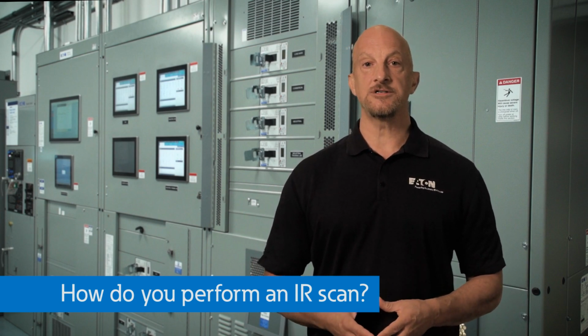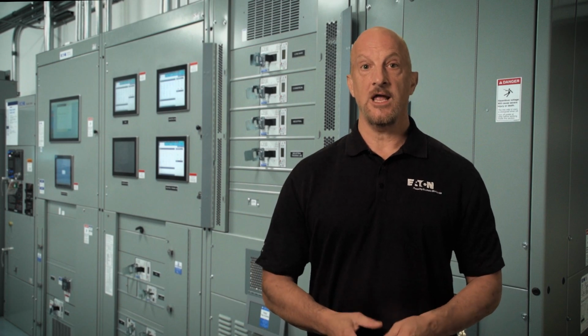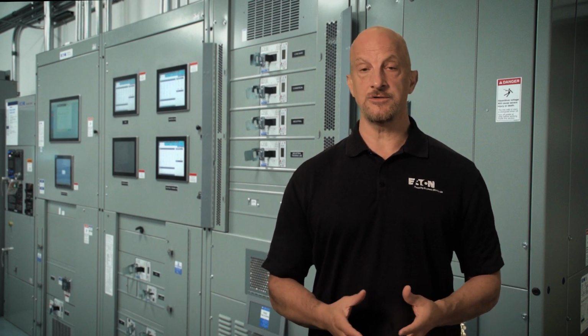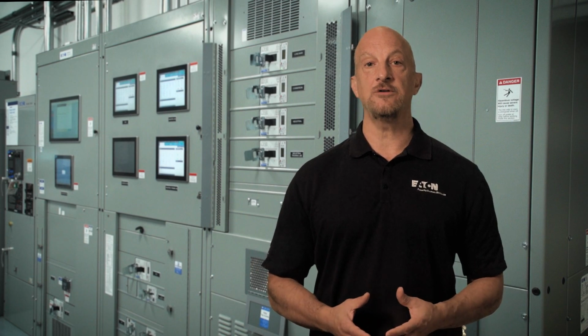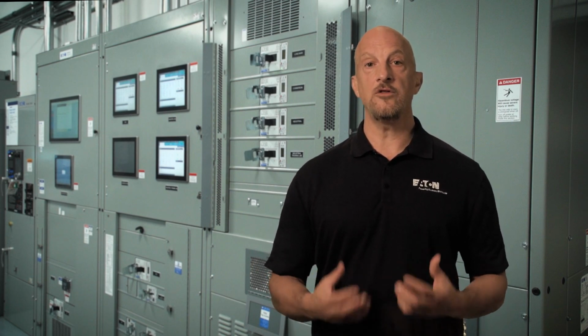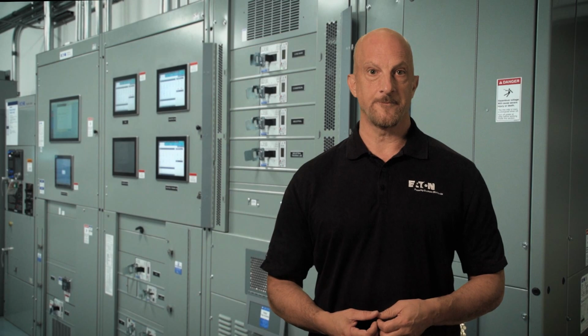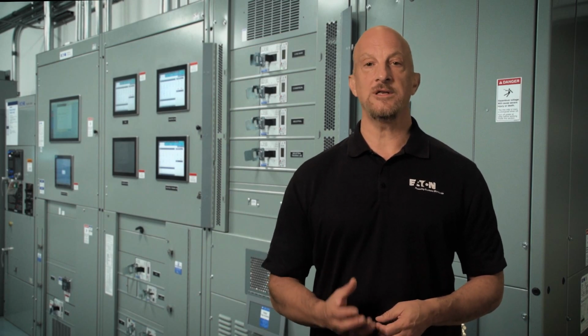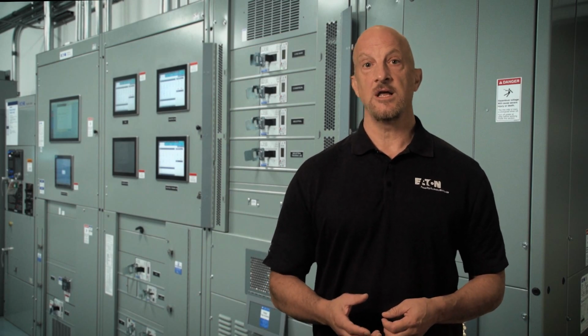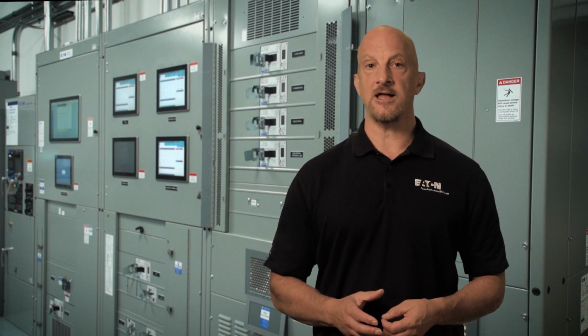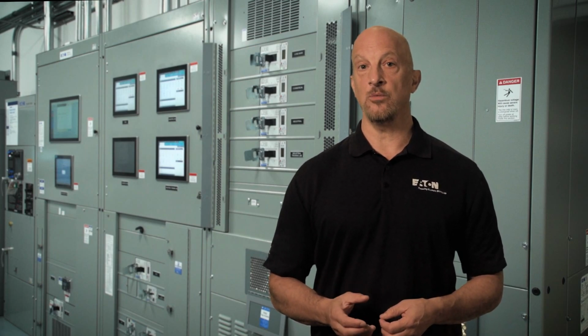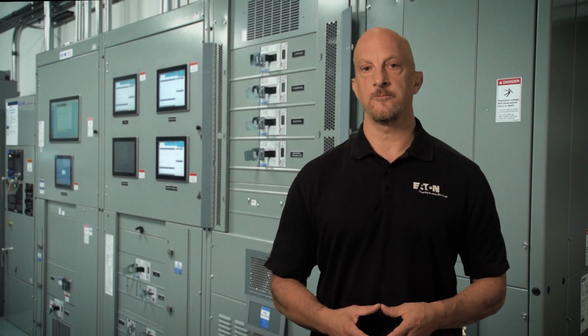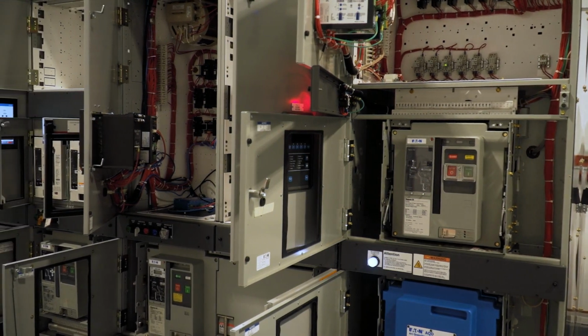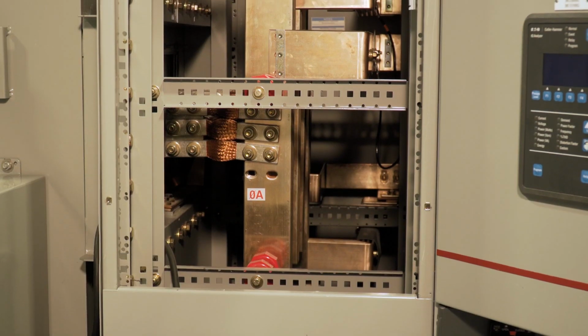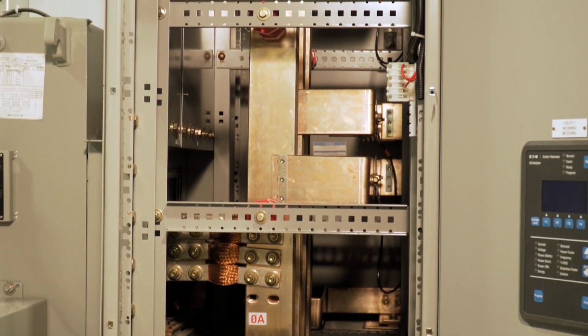In the early days of IR scans, when the cameras were very expensive and you had to attend special classes to know how to use them, the opportunity and cost to do the scans was very limiting, although the benefits proved to be well worth the effort. The early cameras used liquid nitrogen to obtain good thermal images of electrical systems, and because of that, the duration of the testing and the output was typically limited from a time standpoint. So you would normally go around your facility and remove all the panels and covers of the equipment that you intended to scan in preparation to do an efficient evaluation.